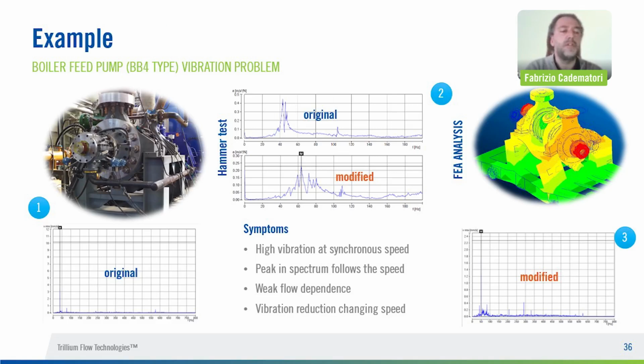In this picture, I want to show you an example of an activity that involves both the aftermarket department and the research and development department. We have a boiler feed pump with a vibration problem, and what do we have to do now? We have to go back to our map and try to understand the symptoms that we have for this pump. In this case, we have high vibration at synchronous speed, a peak in the spectrum that follows the speed, weak flow dependence. And another important point is that vibration changes when we change the rotating speed.